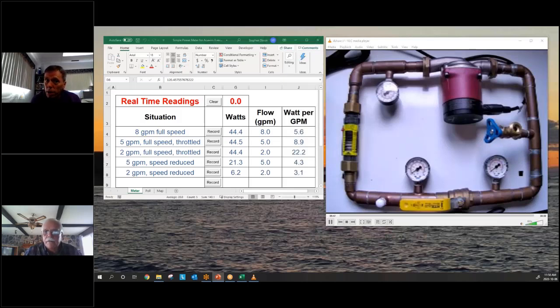Well, then yes. I'll just tell another hint that we have not talked about as soon as you talked about pumping. If you have to prioritize, condensing tower pumps are usually your largest and should be looked at. They're open system pumps. They're subject to potential cavitation. They should be number 1 on your list of investigation. Chilled water pumps should be number 2 because they are larger. The reason they're always larger than heating pumps is because the delta T between the chilled water and the set point you want to achieve in the room is small.